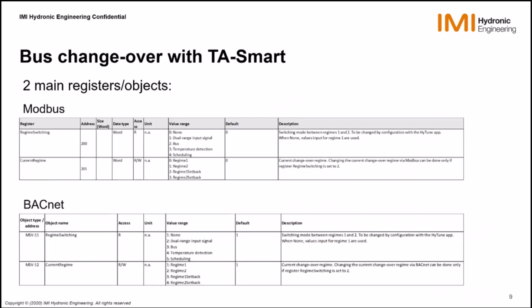In terms of bus changeover with TA-Smart, there are quite a few registers related to that because, as you might have already seen in the list of registers, they are tagged with regime 1, regime 2. We get all the max flows, max values, max power, max position, etc., that can be assigned for regime 1 and for regime 2, clearly. And therefore, we already have a lot of these in the list of Modbus registers.